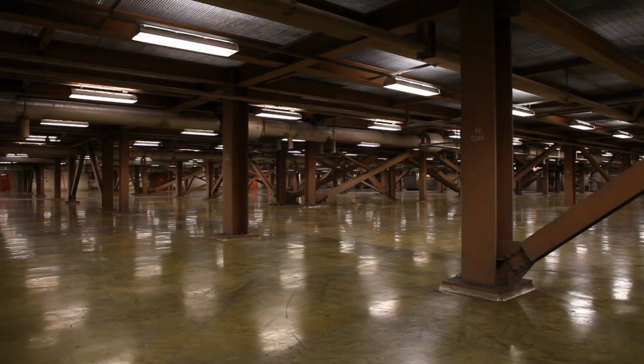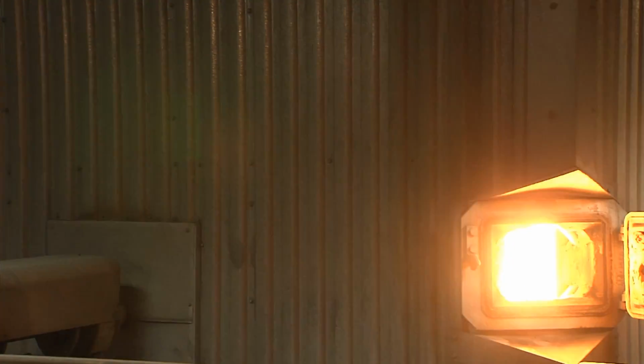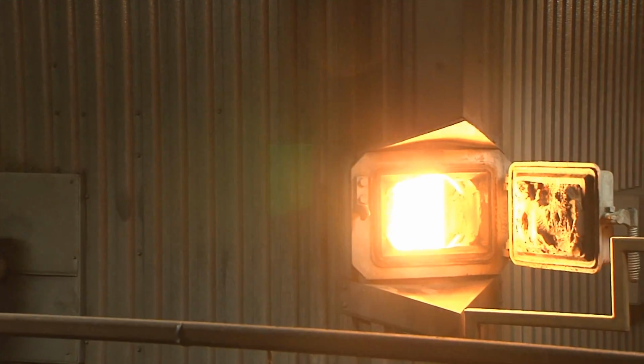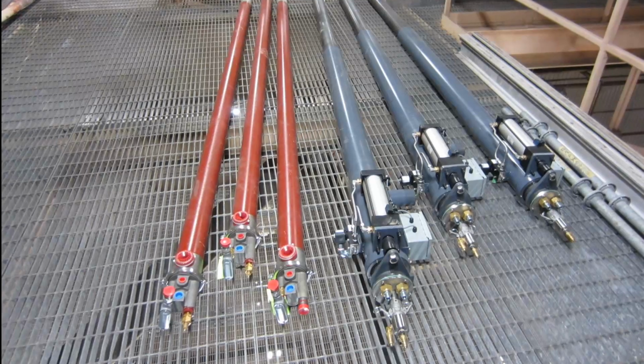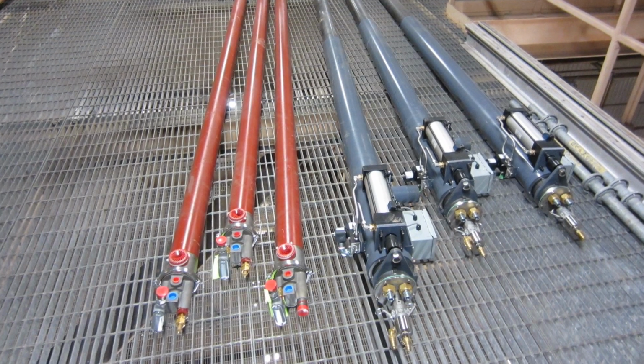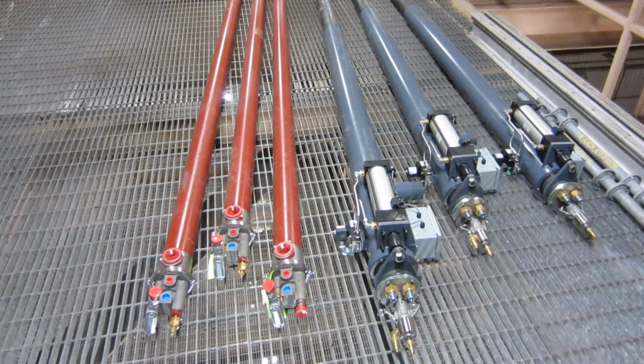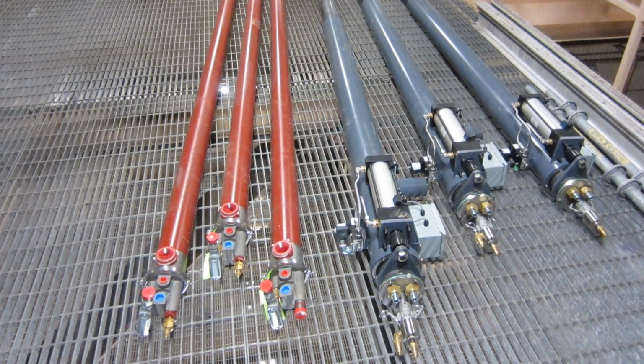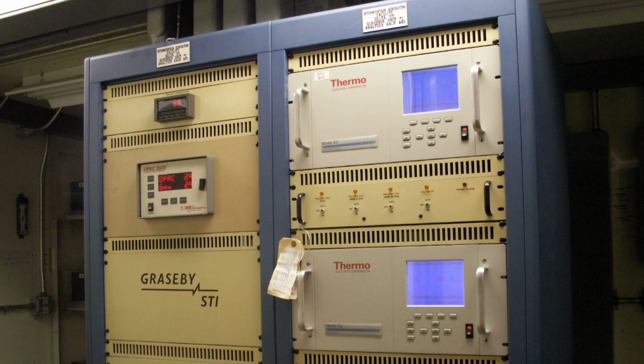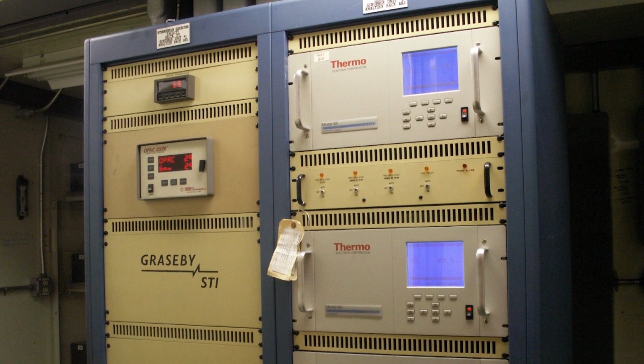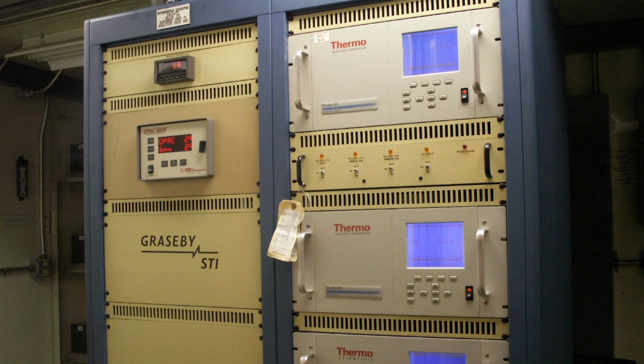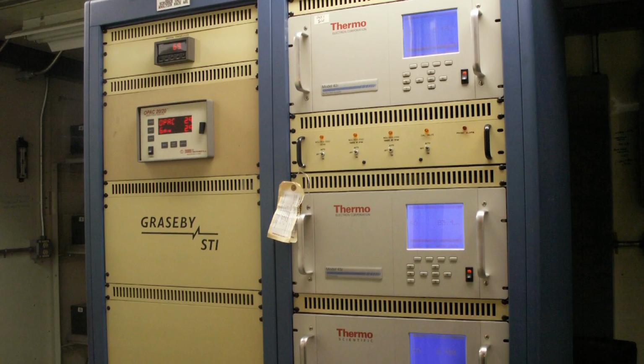MATS, or Mercury and Air Toxic Standards regulations going into effect, will not allow the generating units to bypass the baghouse during startup after 2015. An oil lighter design which lowers opacity is needed so that smoke produced during startup will not foul the baghouse bags. 2 types of retractable lighters were installed and tested during the Unit 2 outage, and they have been in service since. Visual testing, as well as the continuous opacity monitor, verified strong smokeless flames with less than 5% opacity.